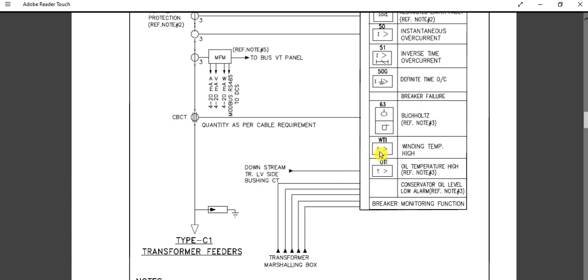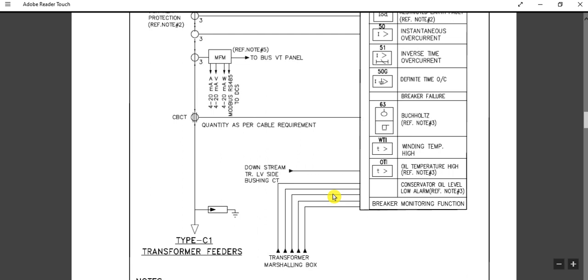On the lower side, as you can see, there is the 63 Buchholz relay and WTI — winding temperature indicator. These are related to oil-filled transformers only. The Buchholz relay is located with the oil-filled transformer, so its signal comes here to the relay. WTI provides winding temperature high measurement, OTI provides oil temperature measurement, and there is also a conservator oil level low alarm signal. These signals come from the transformer marshalling box to this relay.